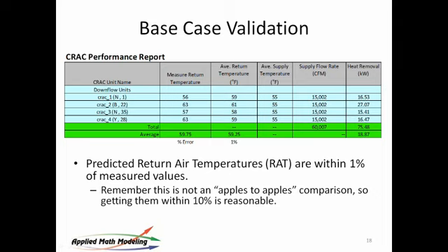a constant either. If you look at the return temperature, there's a sensor somewhere that is measuring the temp in the real world, and it's measuring the temp at a given point on the surface area of the return plenum, usually at the top of the CRAC. But that's only one point. There's actually many points. Remember that temperature is not uniform across the entire return surface of the CRAC unit. And as a result, they're just picking one point.